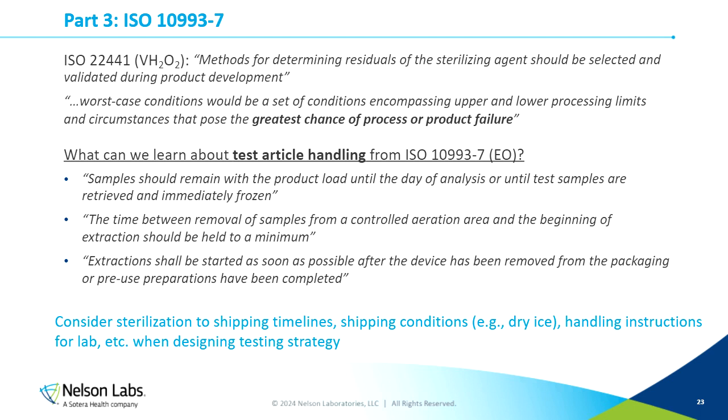If you're not familiar with how the residues testing occurs, what essentially happens is that once the devices are received by the lab, they'll put them in a beaker with a solvent in it. Essentially, just imagine you're dunking the device in a jar of water, but in a very controlled manner, at a controlled temperature for a controlled time. All of the residues that are on the surface of the device should be transferred to that solvent, and that solvent is what's then put through the analytical process. And then the concentration that's detected is back calculated to the amount of residue on our device.